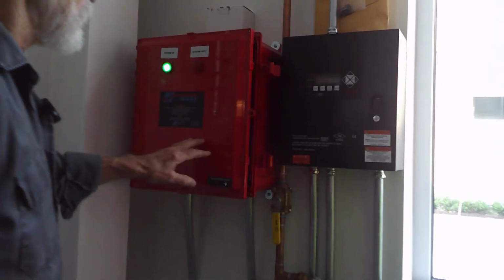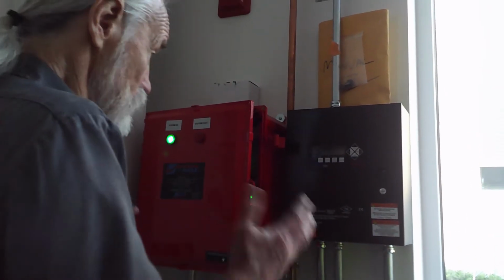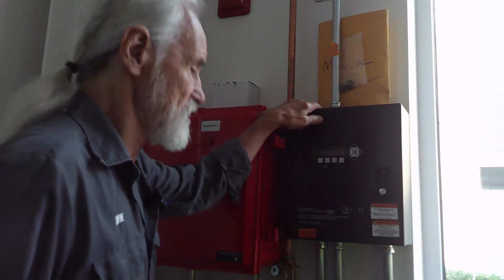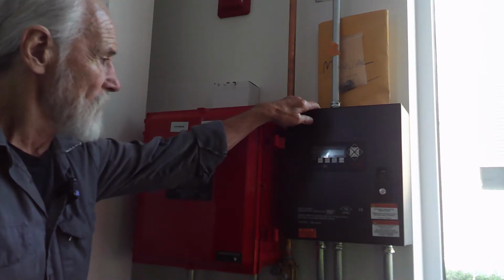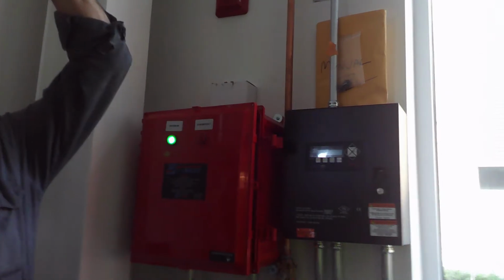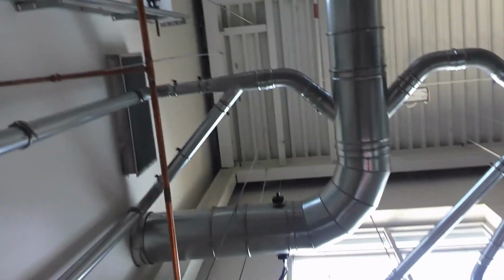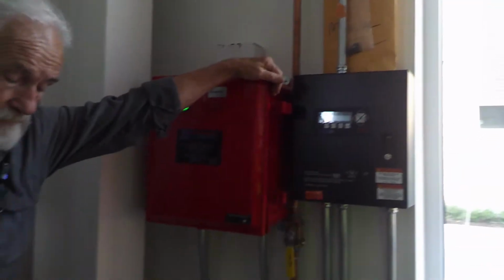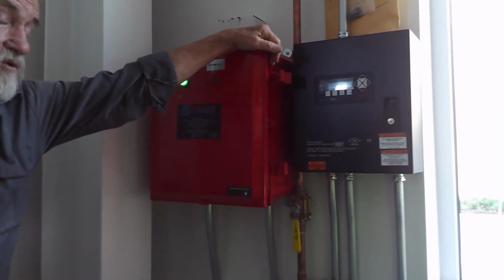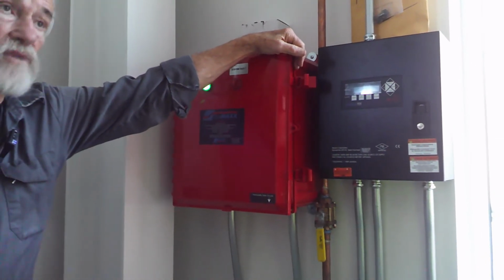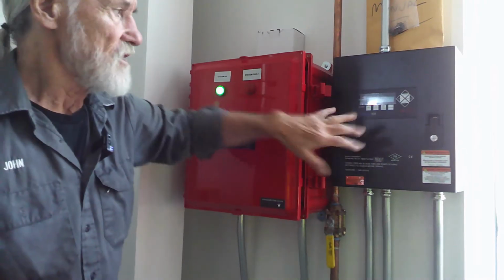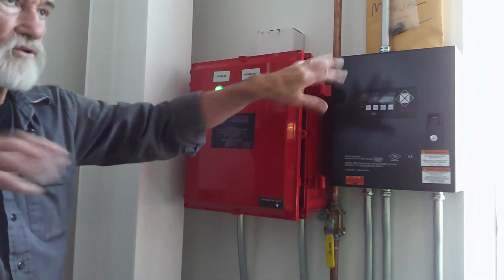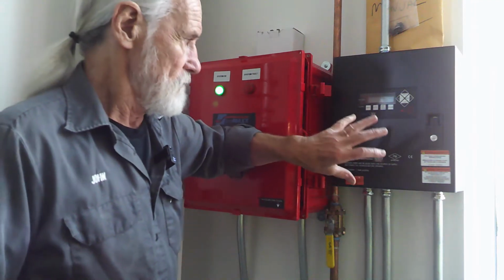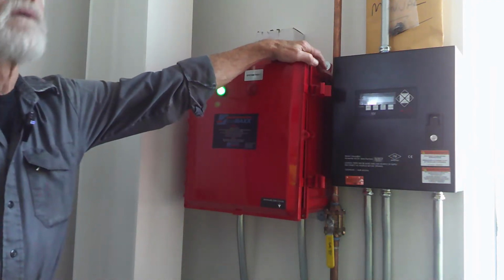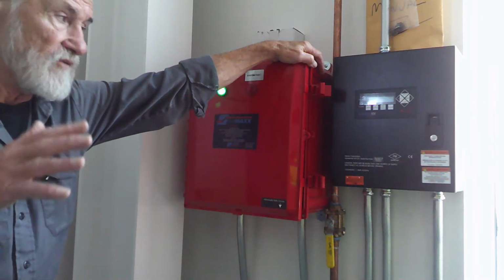Apparently they did the right thing. Okay, these are two separate sort of control systems in a sense. This is a spark detector system. Right above it, you see those two black things on opposite sides? Those are the spark detectors, and they're across from each other for one main reason - they test each other, so you don't have to go up there and try to decide whether this thing's working or not. I'll show you that after I go through the whole thing and push some buttons. So this is the spark detection system. If it detects a spark up there, it goes through a series of events.